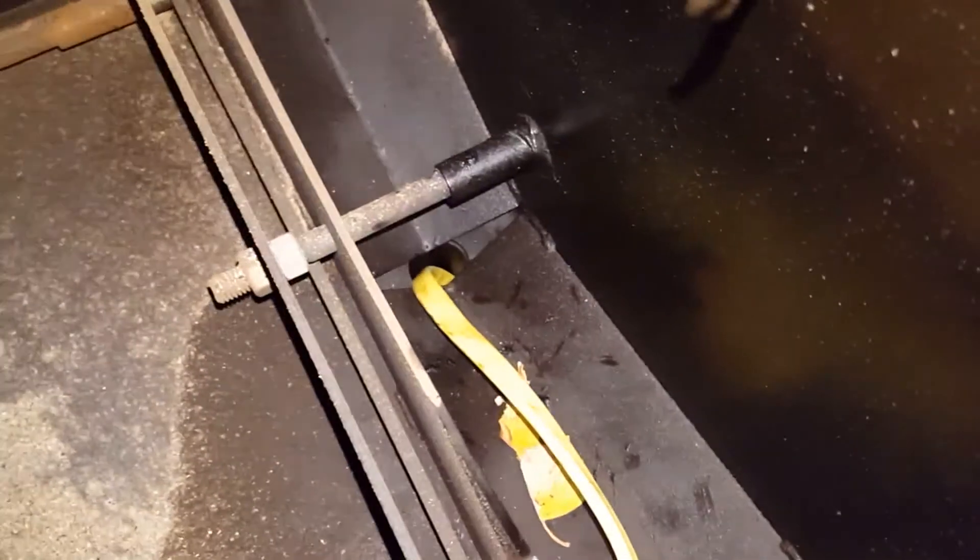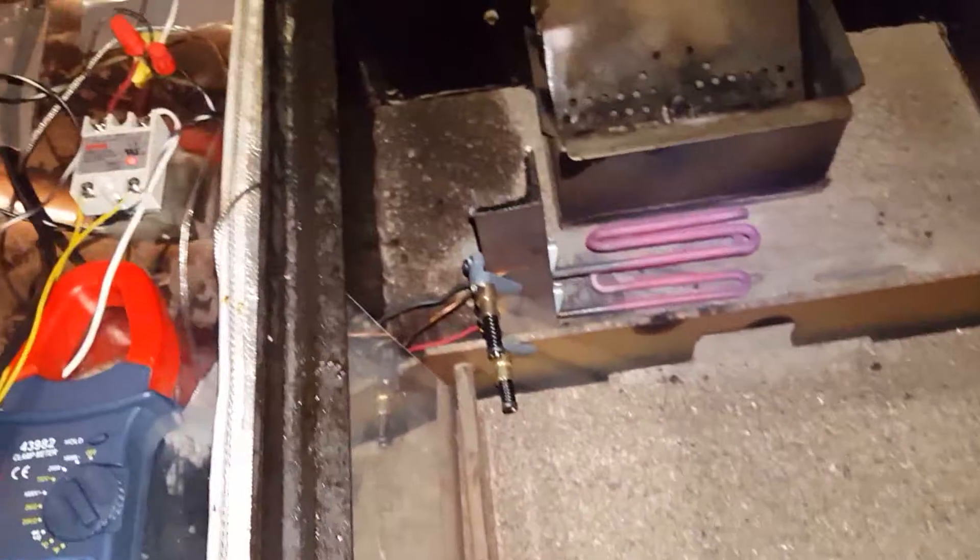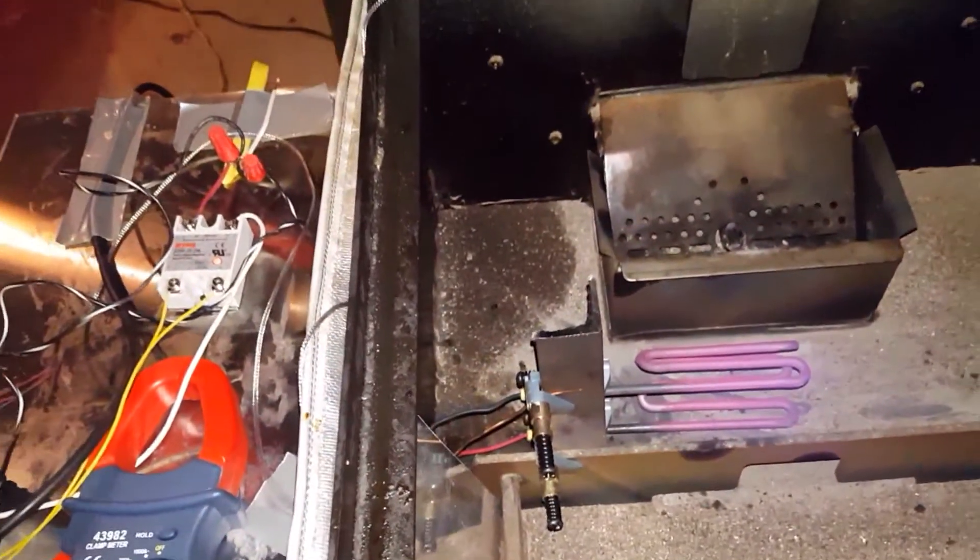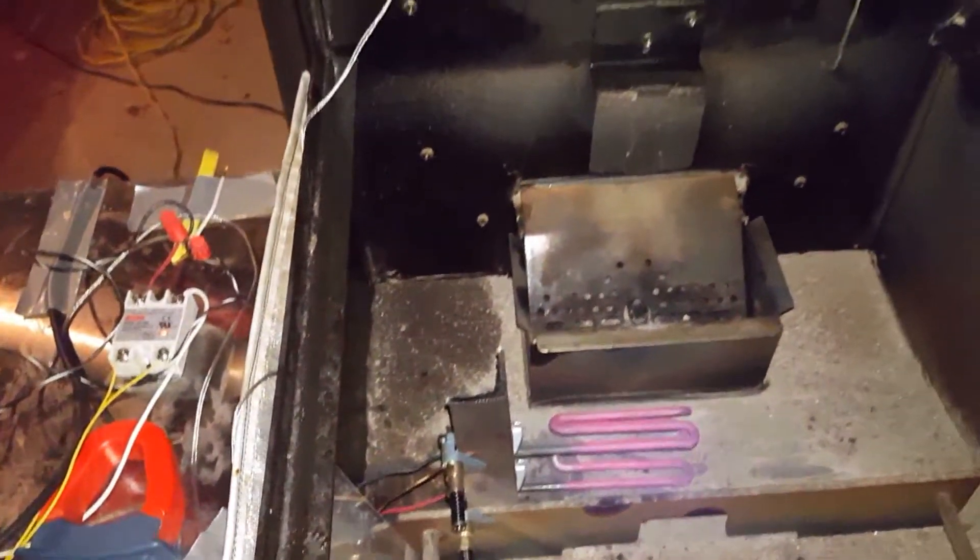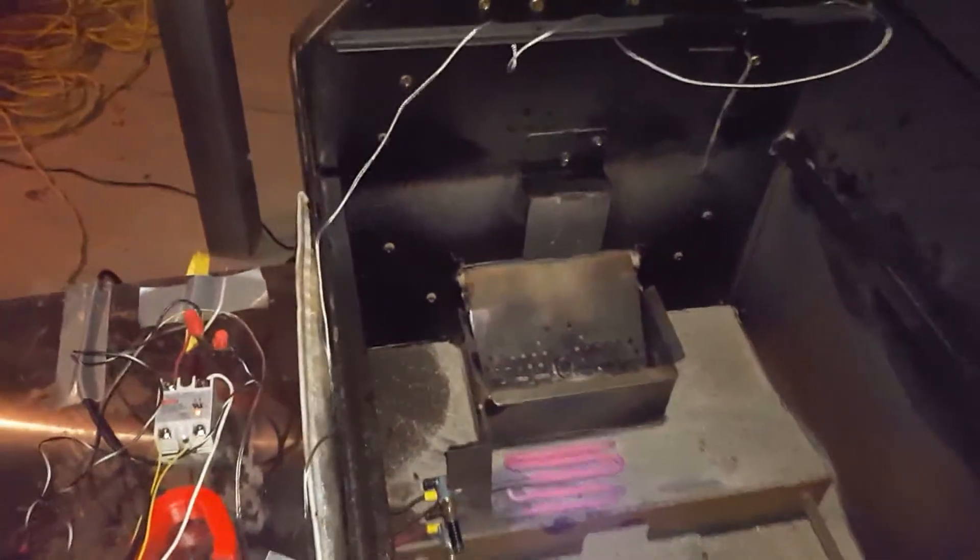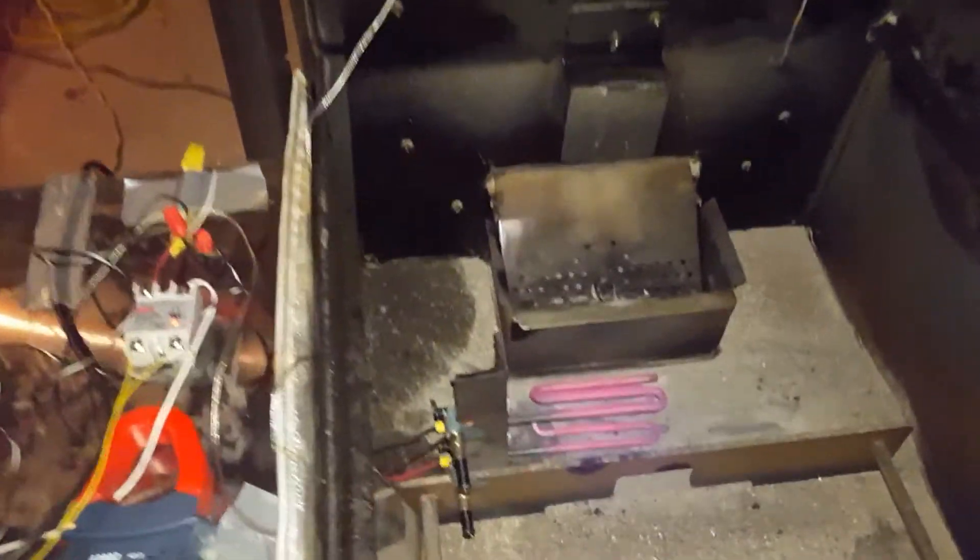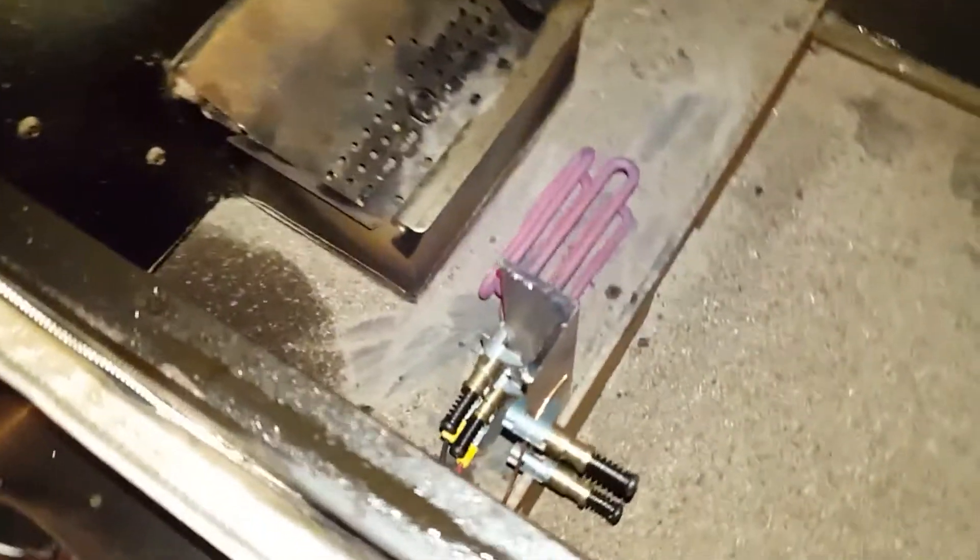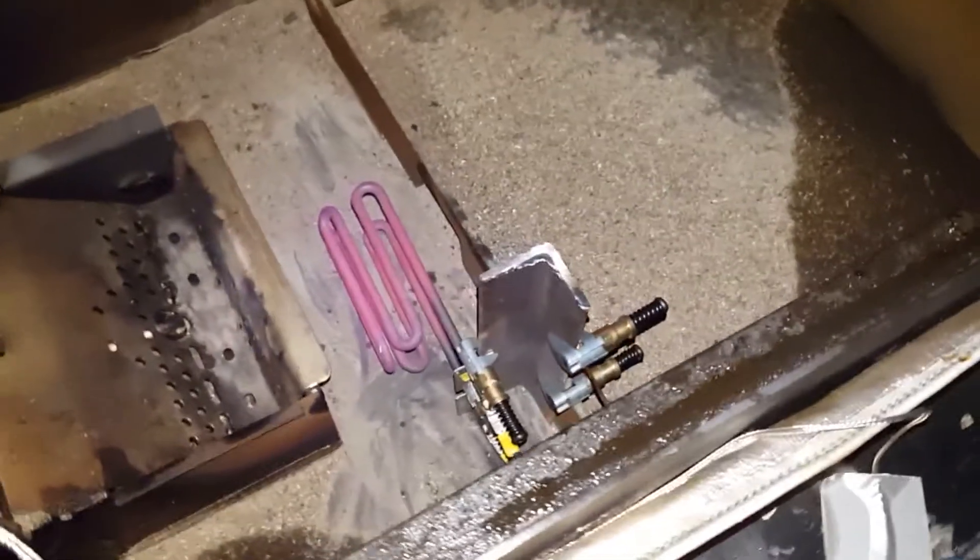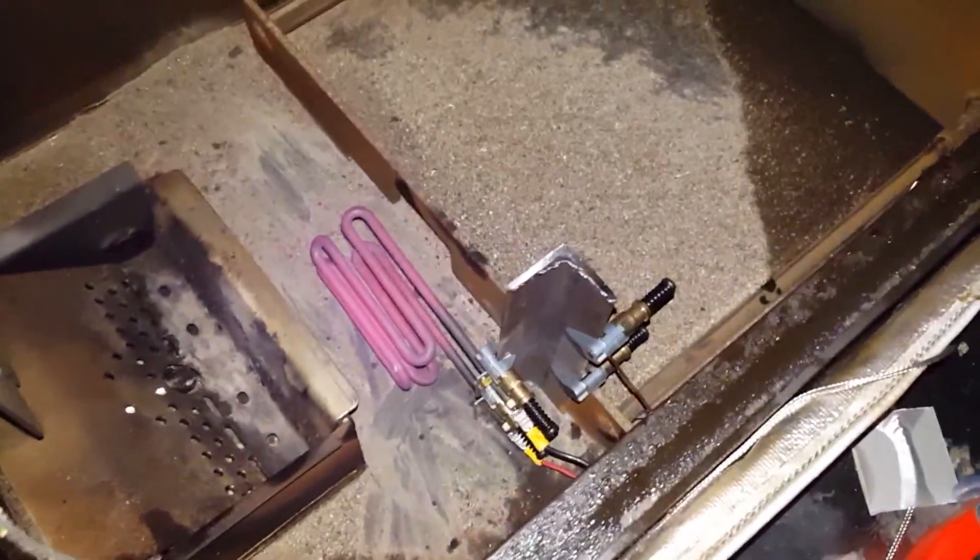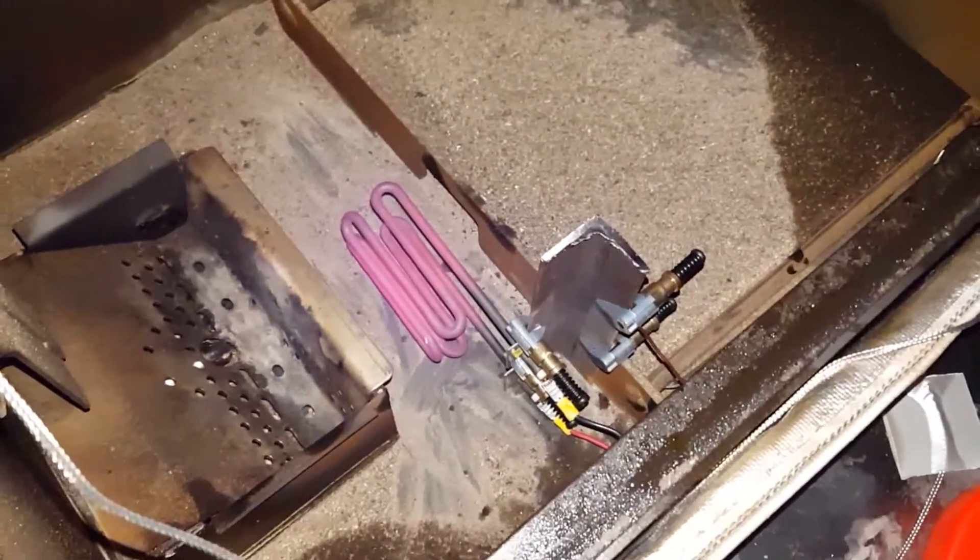And again here's my 12 gauge Romex, nothing fancy. Permanent insulation here will use high heat wire with fiberglass with ceramic coated wire. And if you don't already know, the terminations when you use high heat wire also need to be high heat through either stainless steel or nickel plated things like that.